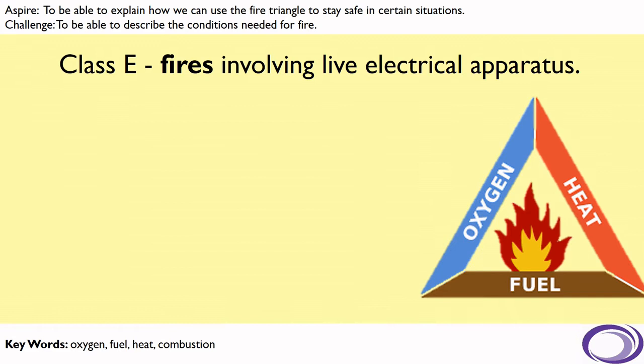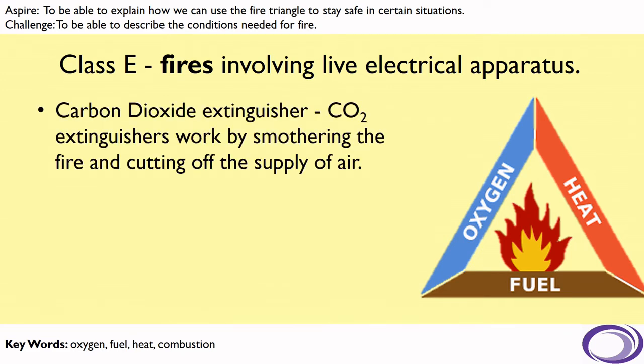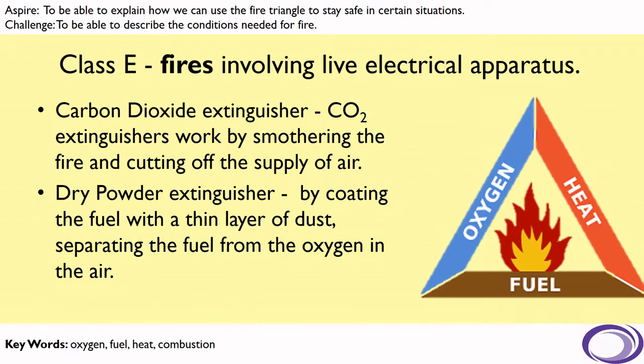Now Class E fires, you could not use a water fire extinguisher because it's live electrical equipment and it is too dangerous to do so. Quite often instead a carbon dioxide extinguisher will be used. That smothers the fire and cuts off the supply of air, removing the oxygen from the fire triangle. A dry powder extinguisher could also be used.